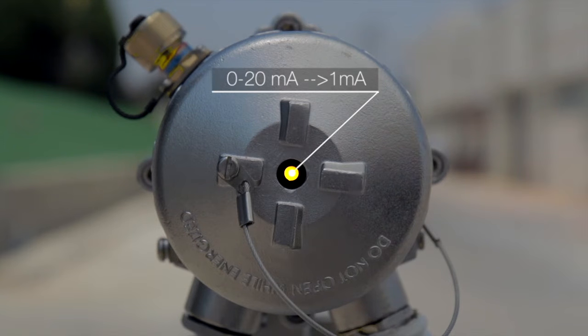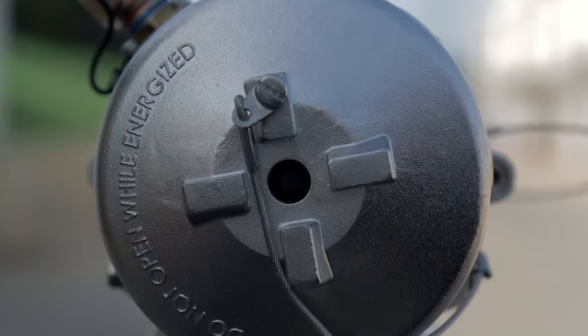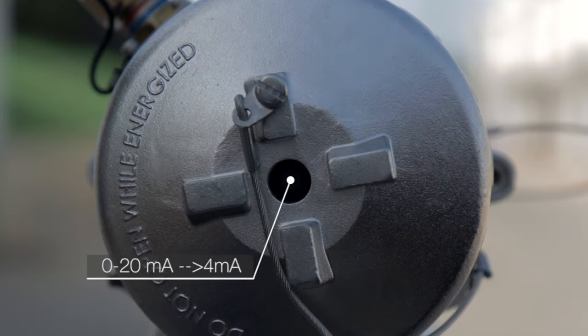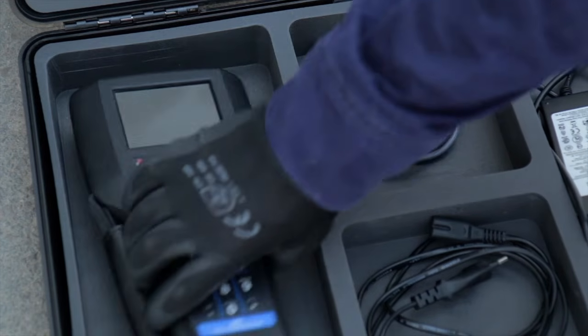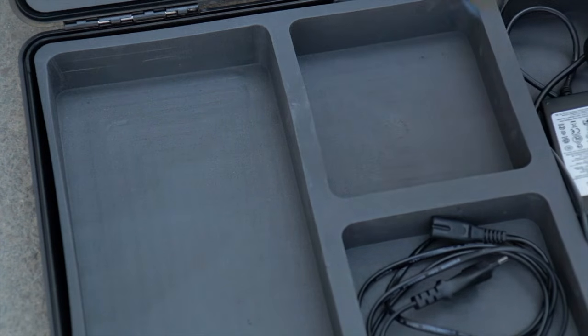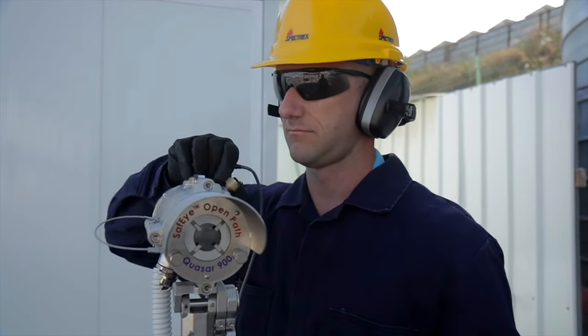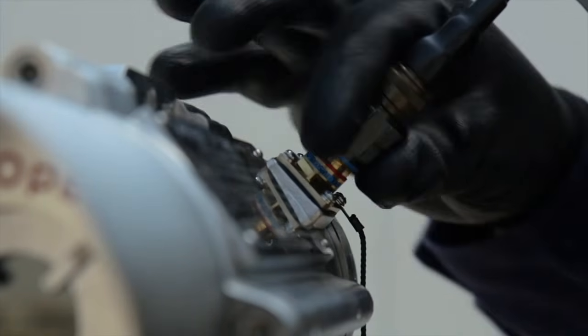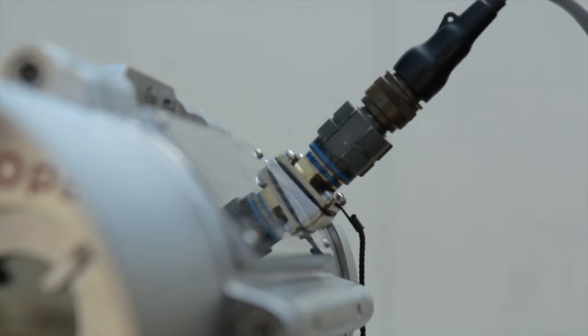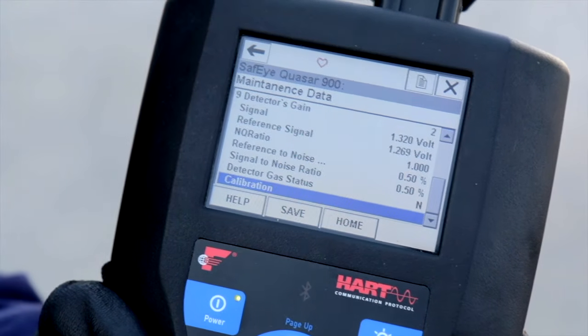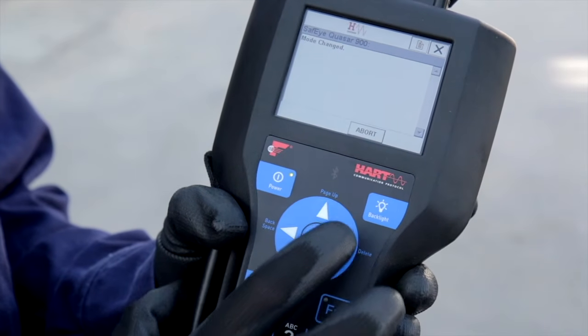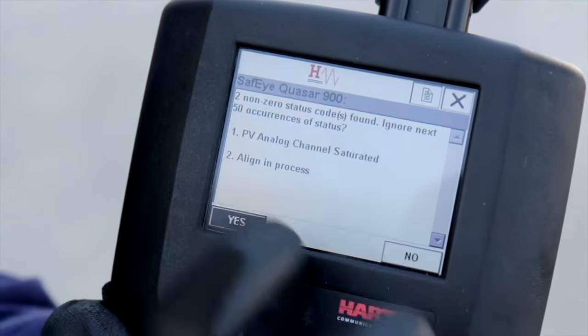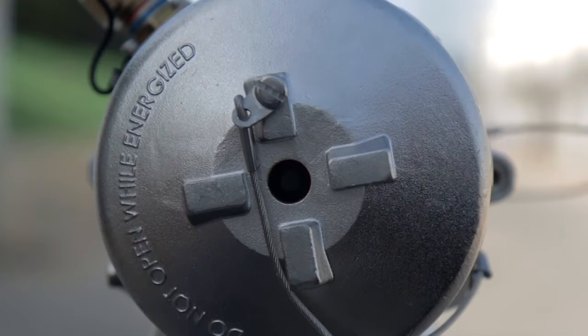The 0 to 20 mA output should now be at 1 mA. Wait 1 minute until the LED returns to blinking green. The system is now back to normal operation. The 0 to 20 mA output should now be at 4 mA. For easier installation and maintenance, you can also use a HART diagnostic unit to perform zero calibration. Begin by connecting the HART handheld unit to the intrinsically safe connector located on the side of the detector. After communication is established, go to the maintenance screen and press the calibration button 3 times and wait until the detector returns to normal working mode.